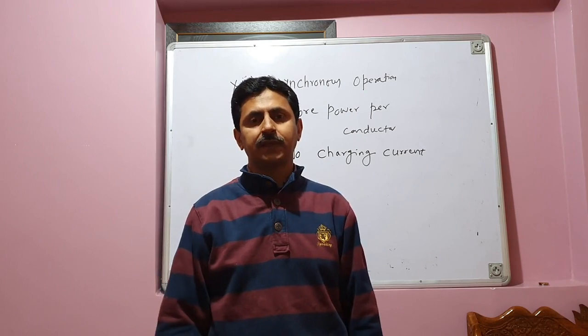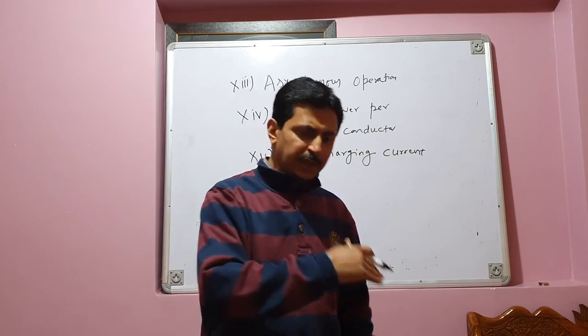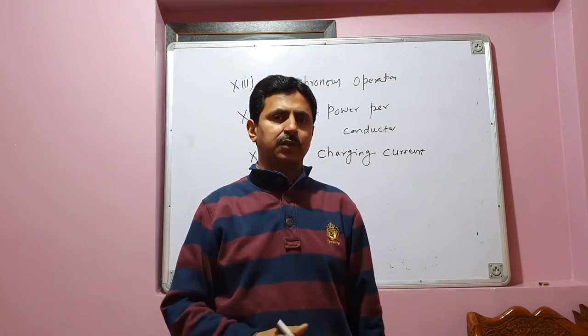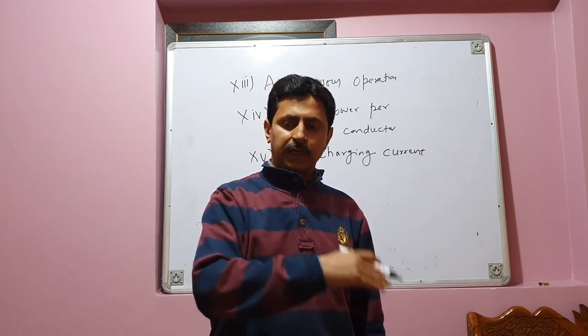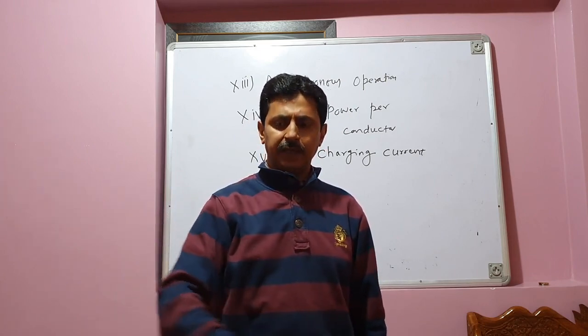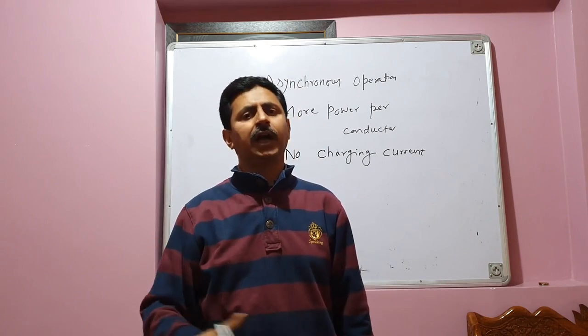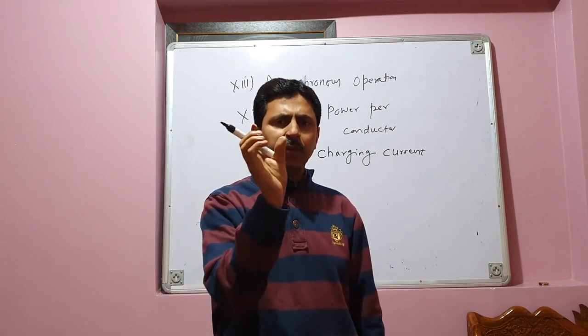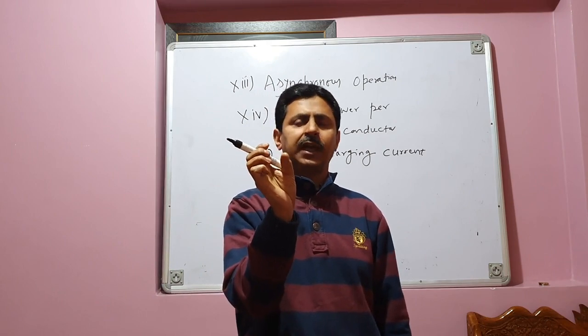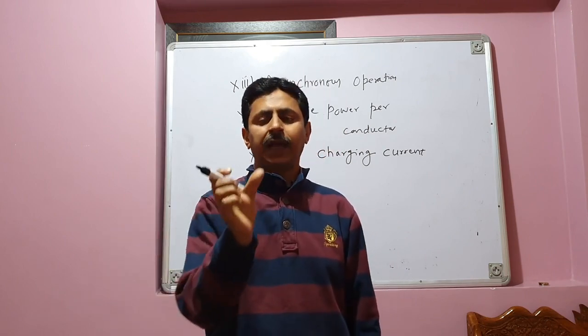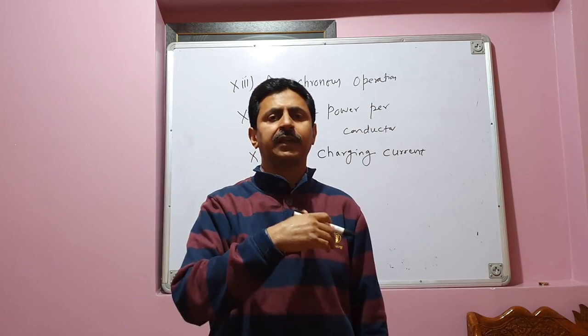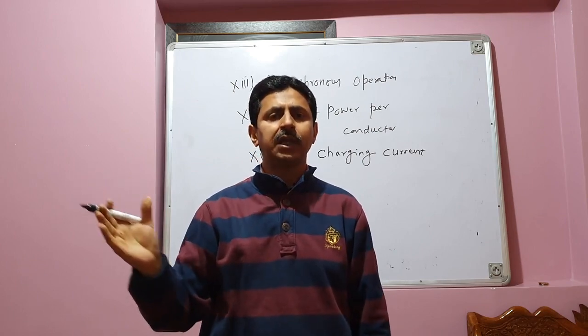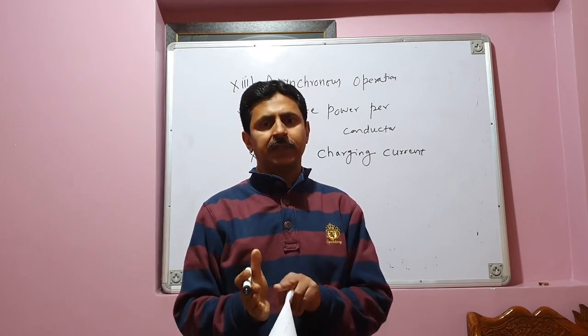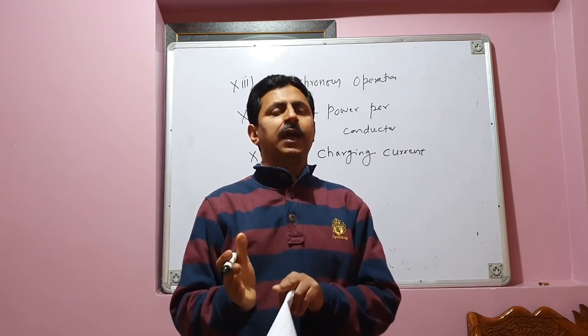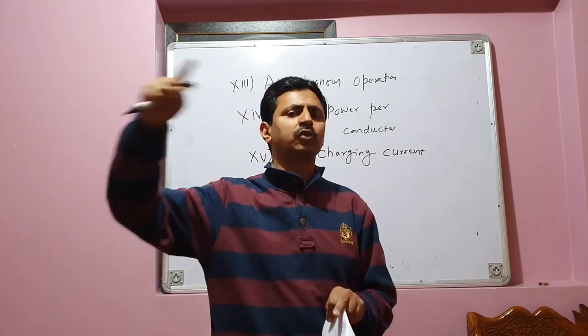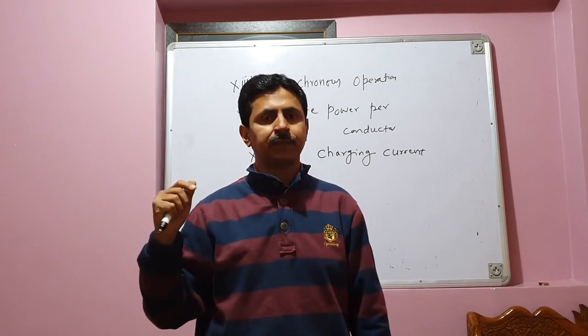In AC, let us suppose we go for underground transmission. In case of AC, the long underground cables are laid under the ground at very high voltage. Since in the cable the conductors are very close to each other and they are buried under the ground, and the conductors are operating at very high voltage, a large capacitance occurs between the conductors at 50 hertz, and that causes the flow of a huge amount of charging current between the conductors in the underground cable.